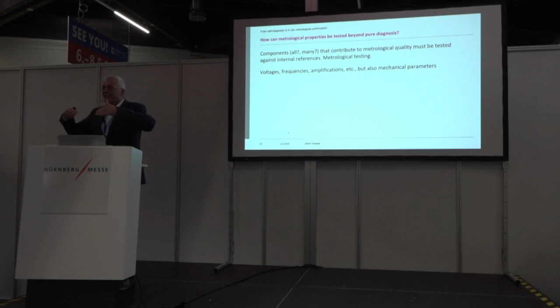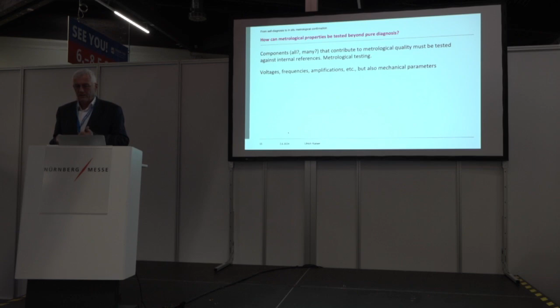Voltages you can check, frequencies you can check, amplification you can check, but also mechanical parameters. You try to find out what the degradation of your device is, which needs regular calibration and adjustment. And then you say, okay, which of these components do I check in order to reduce the probability that calibration is necessary. I have a few examples just to show you.